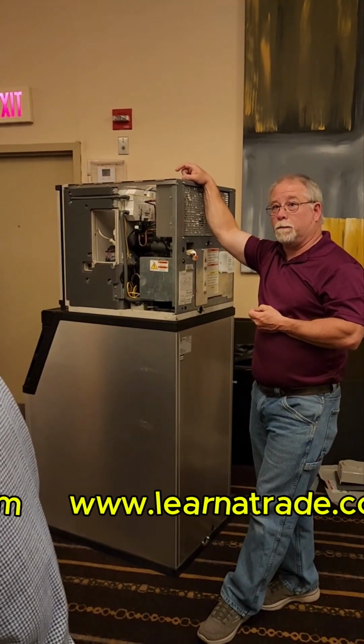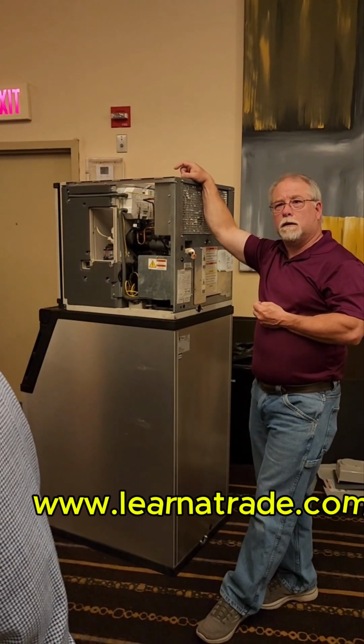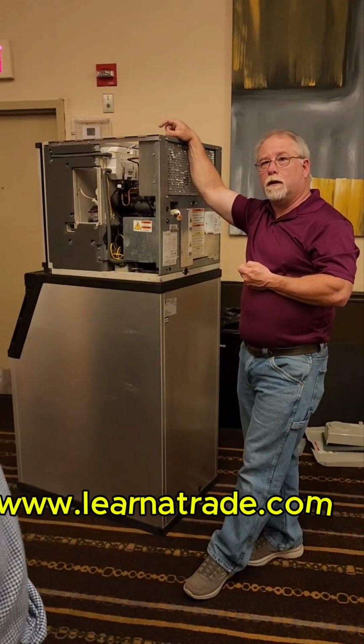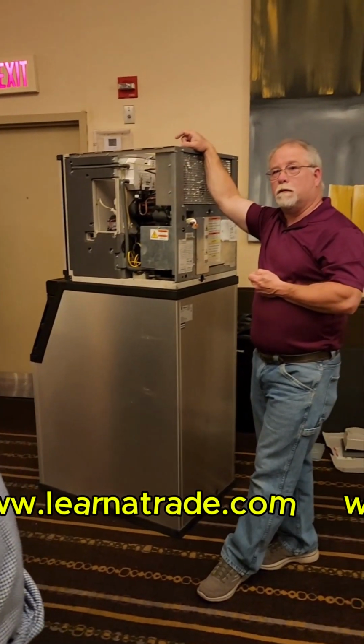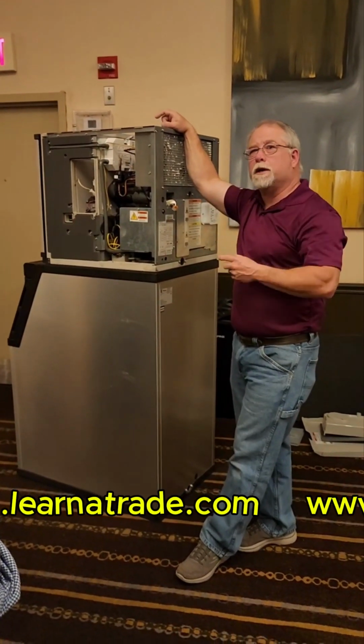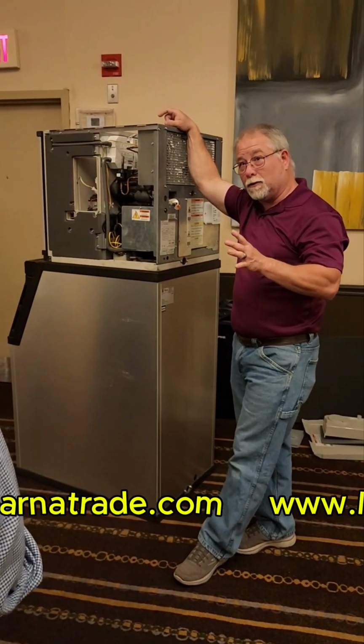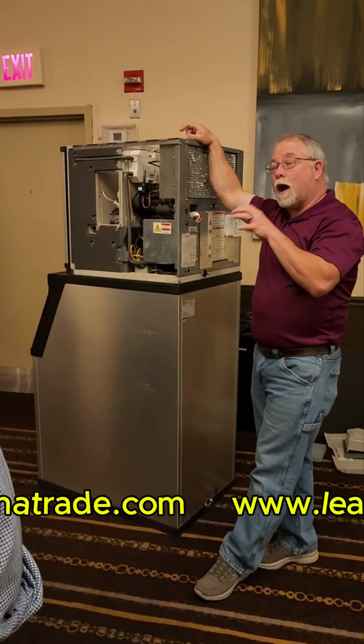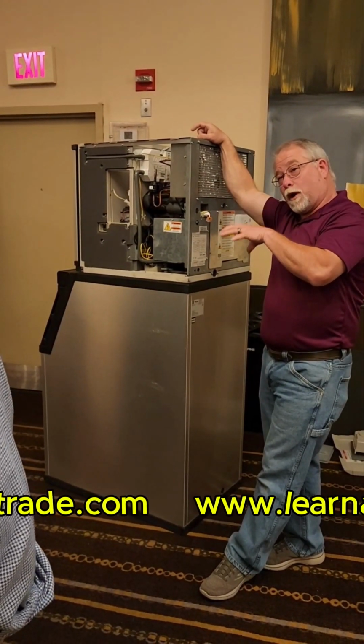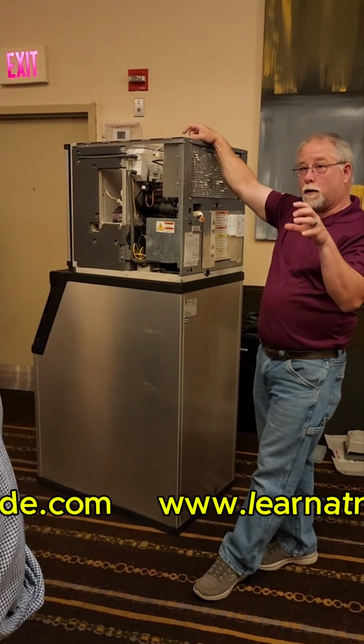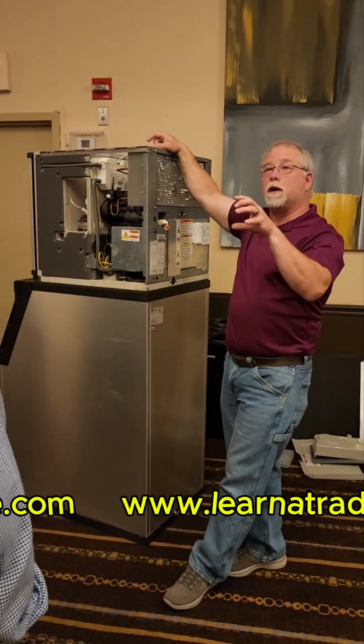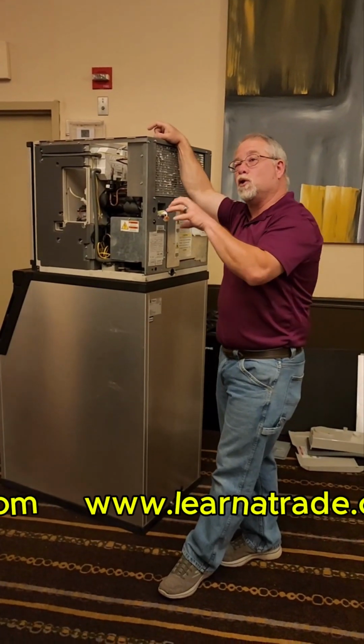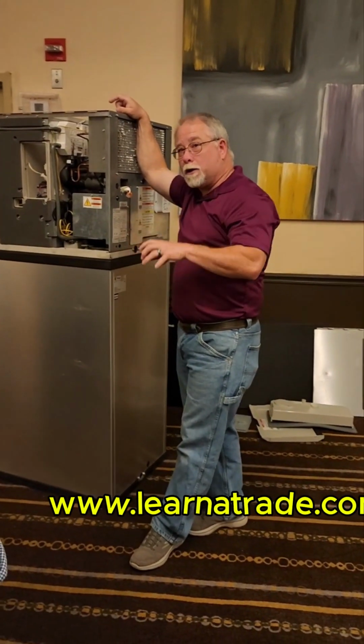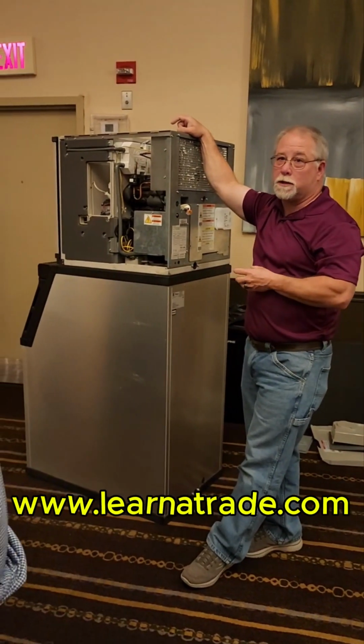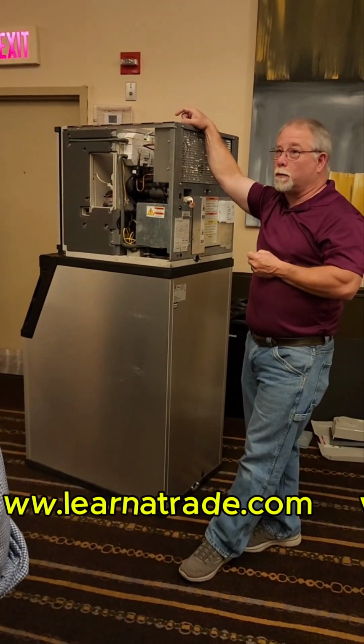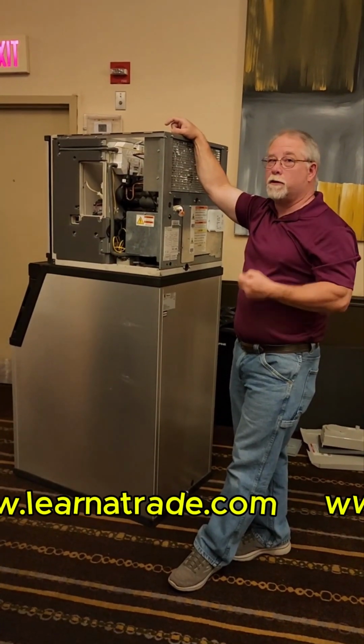Will you guys even talk pressures with us with 290? Yeah. I've had other manufacturers say they won't even talk about 290 pressures, they don't even know. We'll talk about it, we've got all the documentation on what it should be. But still, even if the pressure's correct, not having the correct components could still harm it depending on what stage of the refrigeration cycle you're in, and could have a negative effect on the efficiency of the machine. The goal is maximum efficiency.